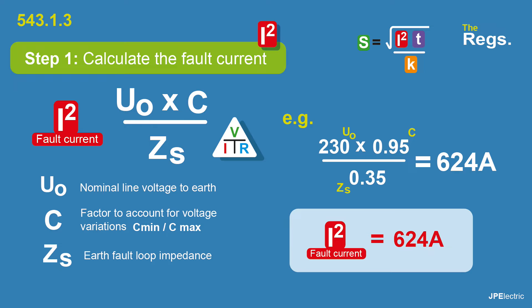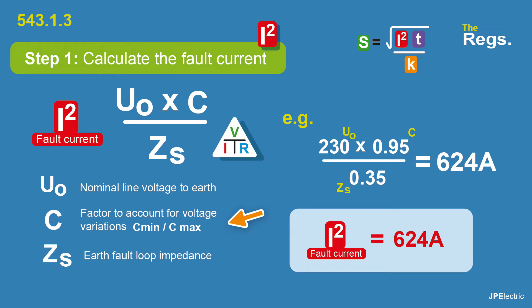Step one is to calculate the fault current — just a bit of Ohm's law. Voltage divided by resistance gives you current. The voltage is the nominal voltage to earth, in this case 230 volts. We have a correction factor known as Cmin to account for voltage fluctuations — we multiply the voltage by Cmin, which is 0.95, and divide by ZS. So 230 times 0.95, divided by 0.35, gives us a fault current of 624 amps.